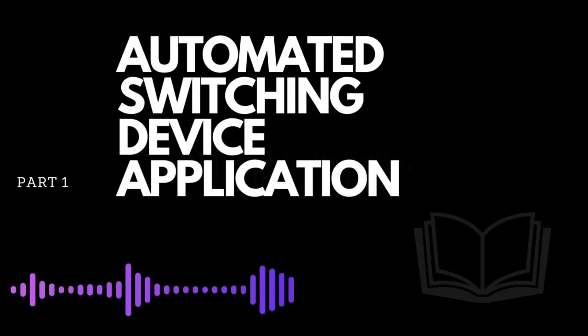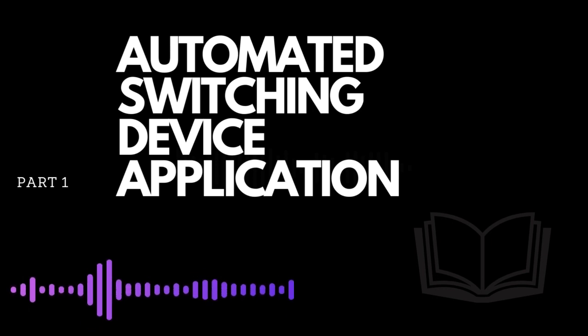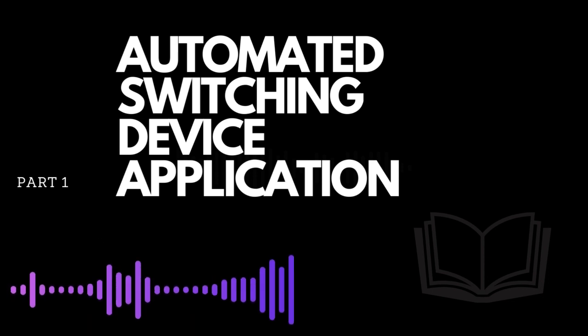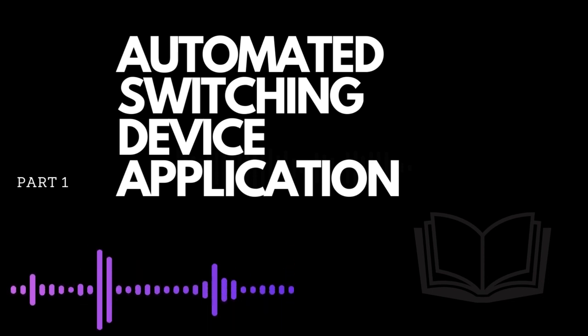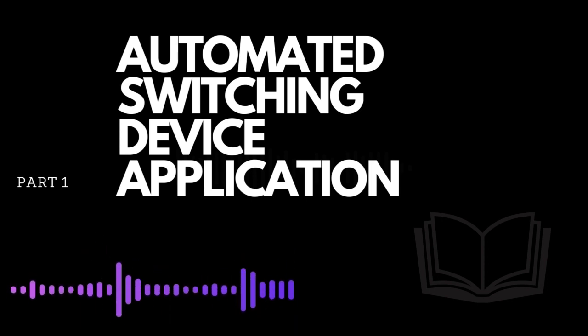1. Introduction. Switching operations are a major source of power system transients. For instance, capacitor bank switching can create current surges and overvoltage. Energization operation can create a significant DC offset that can, in turn, saturate power transformers. Shunt reactor de-energization can cause CB reignitions that can result in equipment failure.